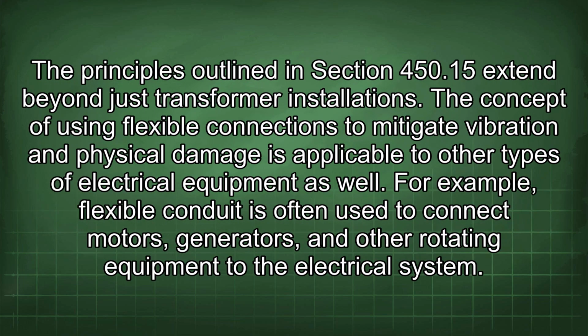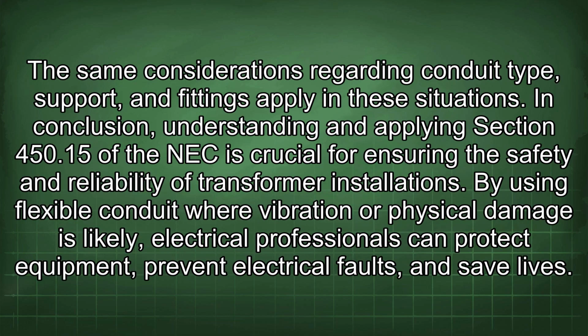The principles outlined in section 450.15 extend beyond just transformer installations. The concept of using flexible connections to mitigate vibration and physical damage is applicable to other types of electrical equipment as well. For example, flexible conduit is often used to connect motors, generators, and other rotating equipment to the electrical system. The same considerations regarding conduit type, support, and fittings apply in these situations.